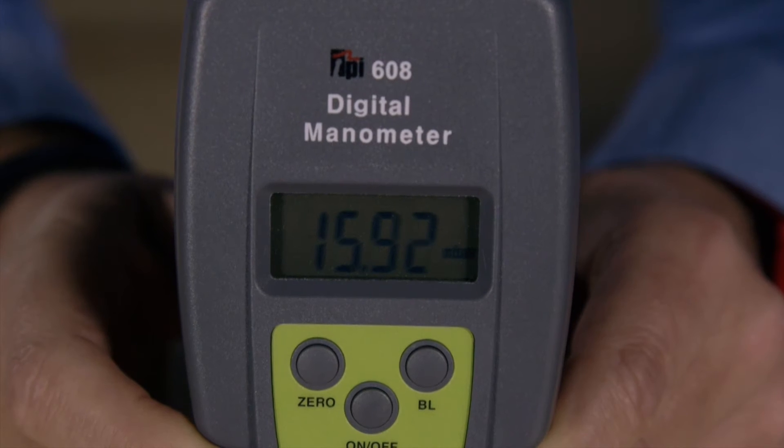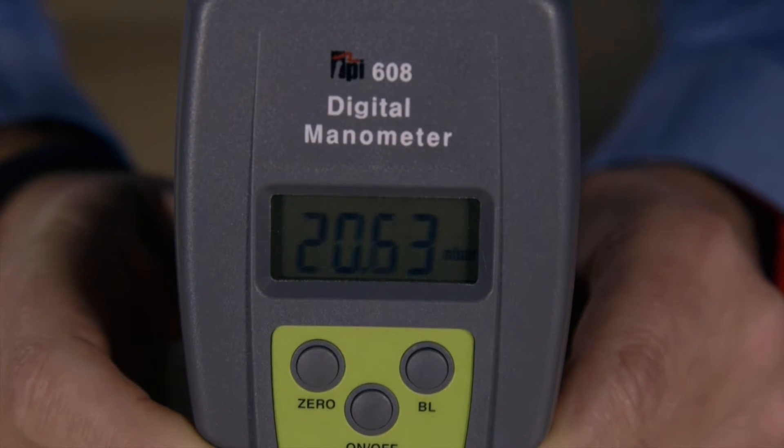It has a two decimal point resolution with a plus or minus 150 millibar range, making it perfect for burner pressures and tightness tests.